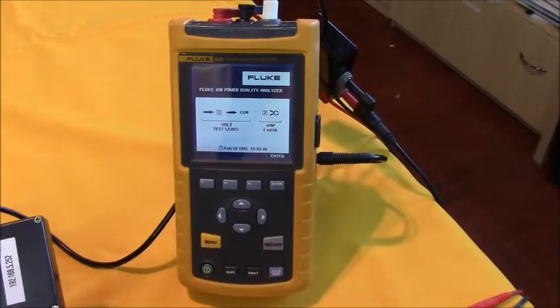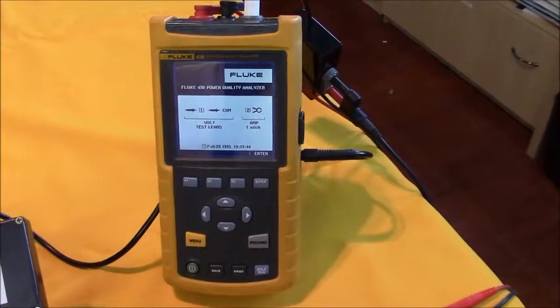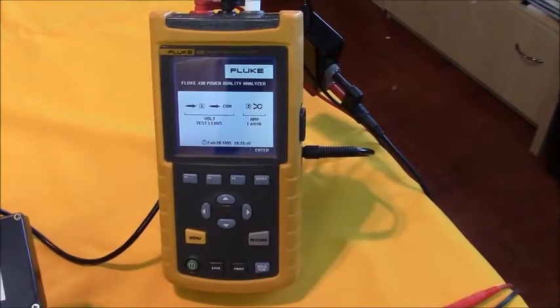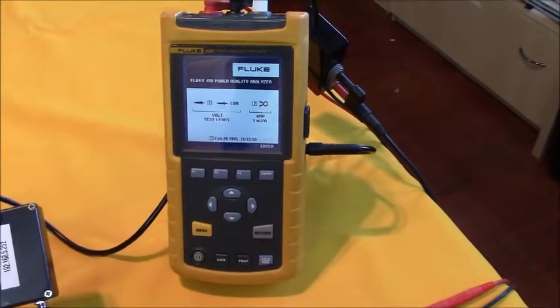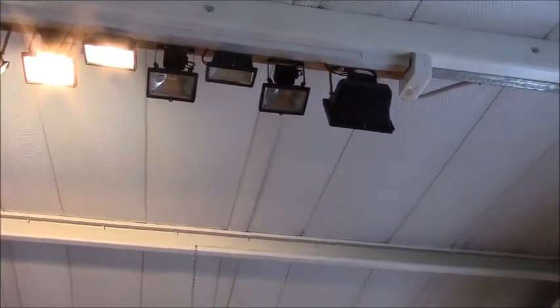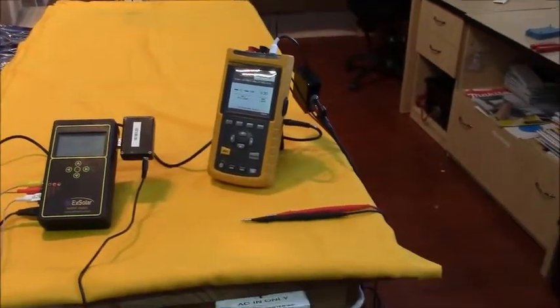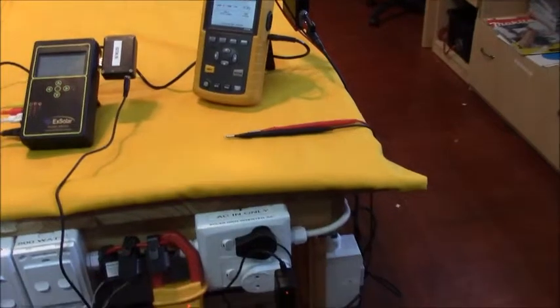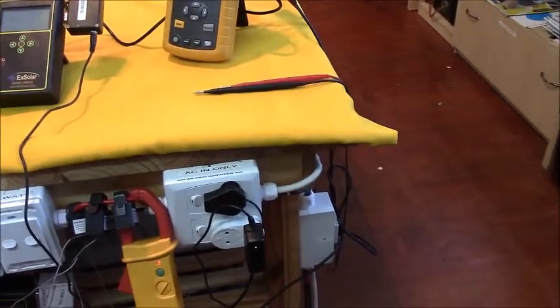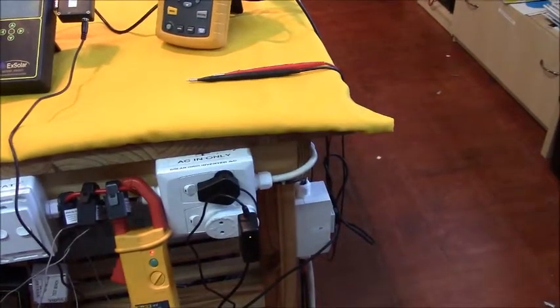You must use a high quality instrument for the calibration, which is in itself being calibrated to a high standard. The load that we're going to be using is going to be a resistive load. In our case, it is some lights which we can turn off and on depending on the requirement, and the power source for both the instrument and the calibration unit must be from the same AC source to prevent earthing issues and floating voltages.